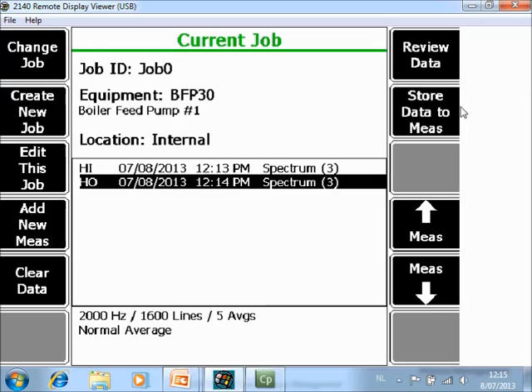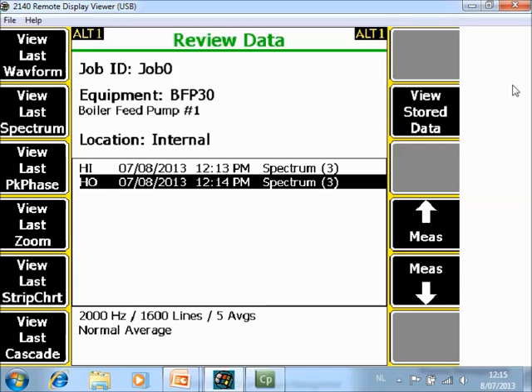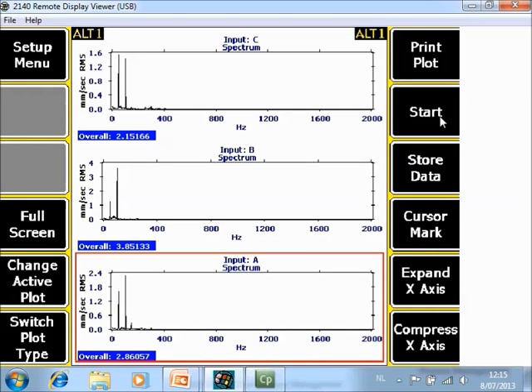If you want to review the data now, go to F7 review data. And then you can choose between reviewing waveform spectrum. If there was peak phase data available, you have peak phase, and so on. So let's take an example. This is the active line. View stored data. And here are the three spectra.